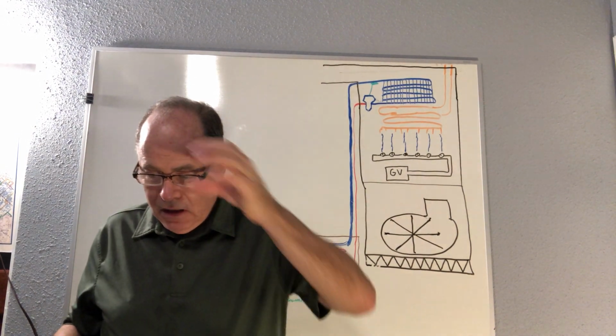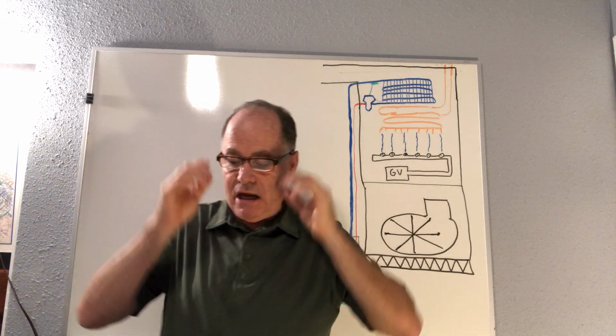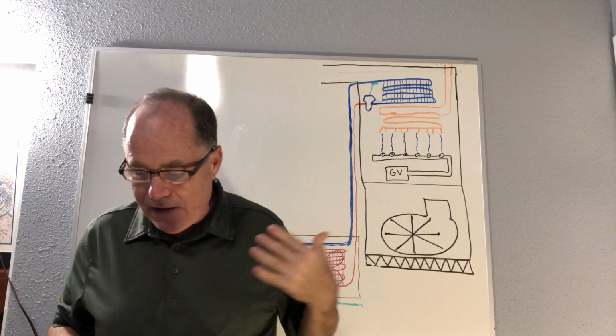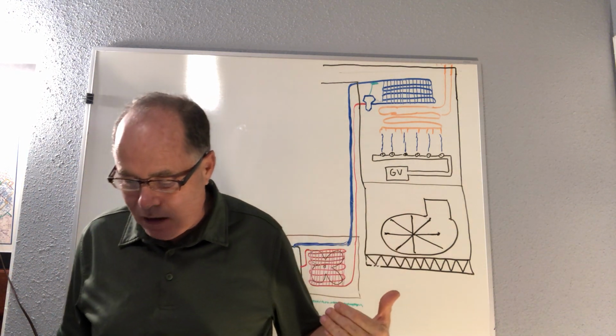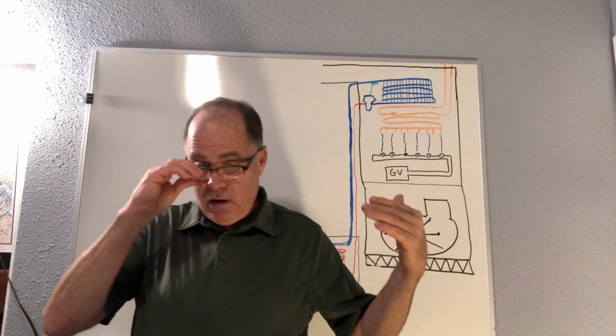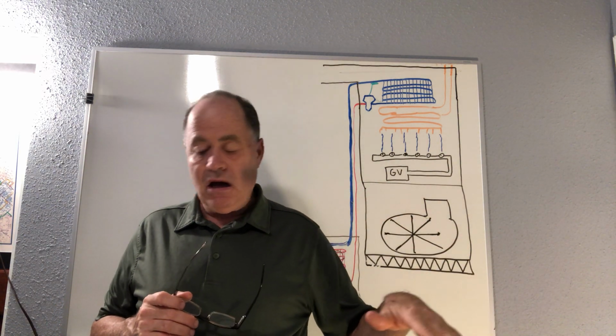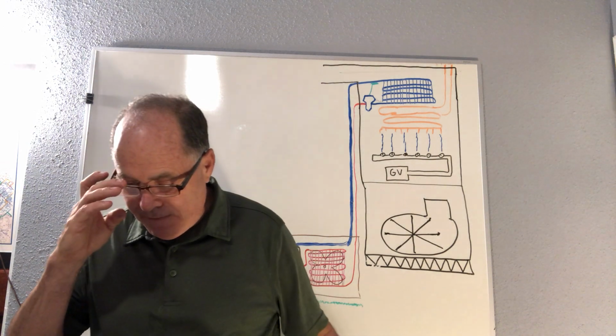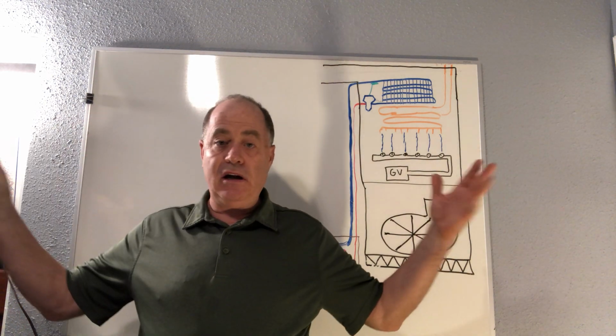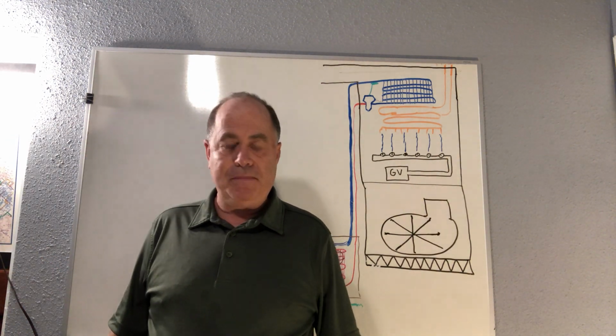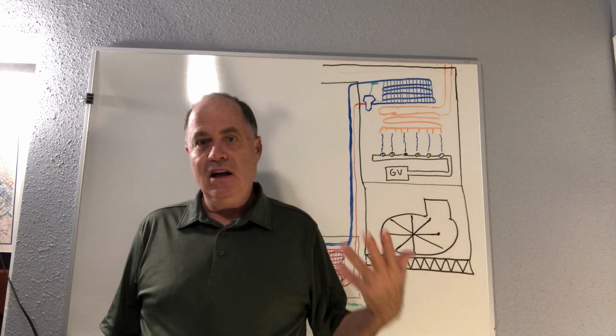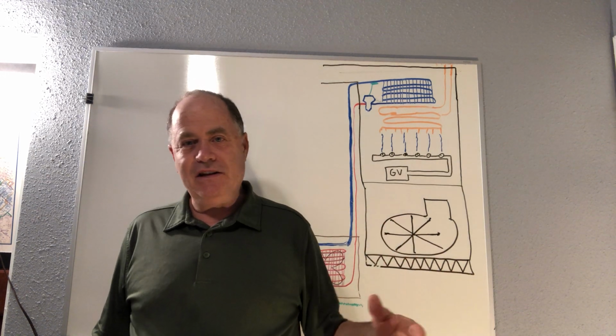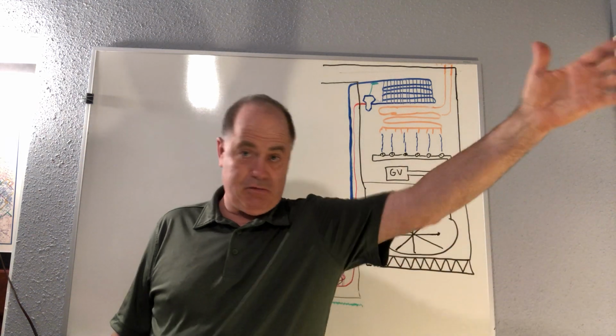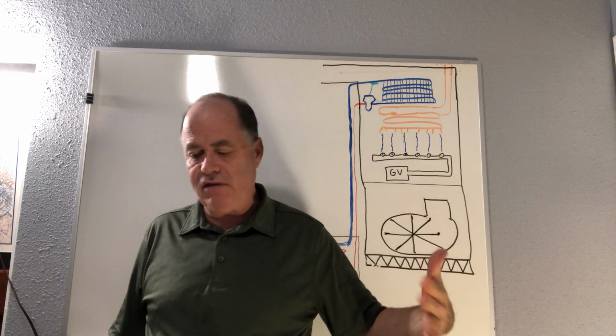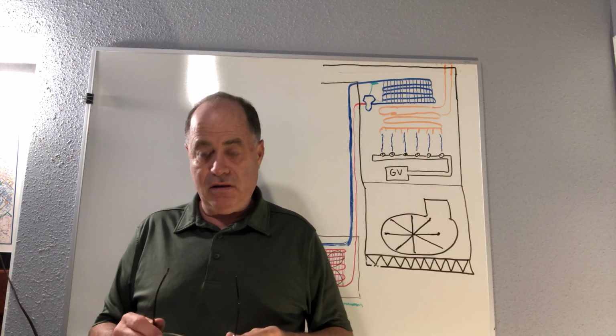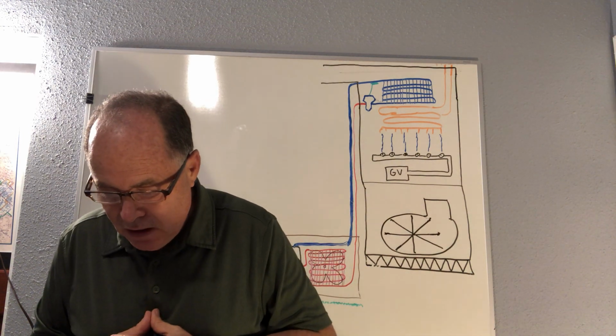Let's move along. Switches in electrical supply lines. It talks about you have to have a disconnect or a way of shutting off the power, and it has to be within sight of the equipment and within 50 feet. So you can't just say, well, I've worked on rooftops bigger than the size of football fields, really, and you can't say, well, 100 feet over there, it's by a straight shot, I can see it. You have to have a means of disconnect there near the unit, okay?